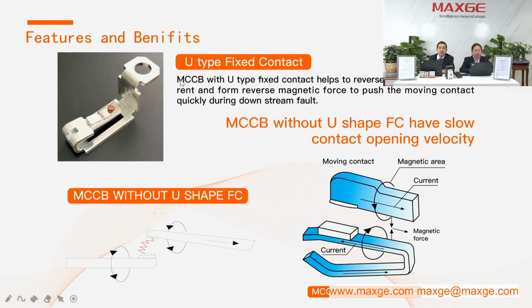And in the next slide you can see we use the U type fixed contact. The unique design of the U type fixed contact helps the moving contact open as quickly as possible, because the current moves from here to here, and then again in the moving contact. The electromagnetic field is generated this way, and here the electromagnetic field is this way. So a repulsion force is generated between the fixed contact and the moving contact during short circuit conditions, which helps the moving contact open very quickly. Normally competitors don't use this type of fixed contact design, they use a flat type design, wherein the moving contact cannot open so quickly, and finally it will affect the short circuit breaking capacity.